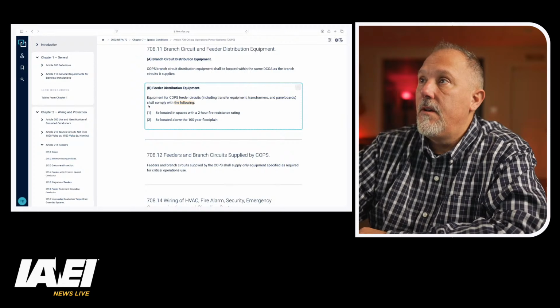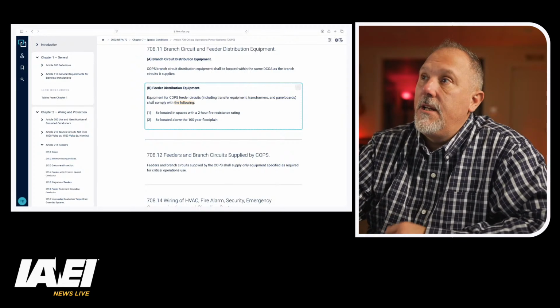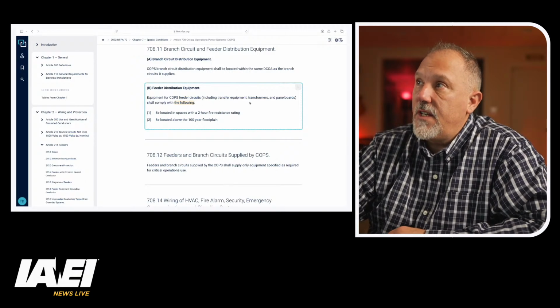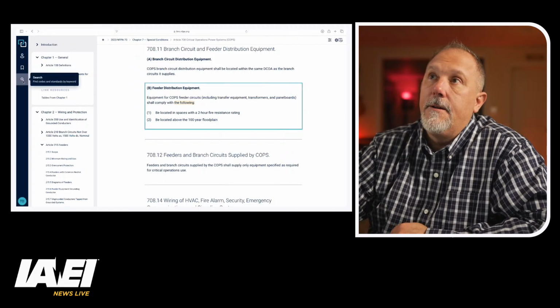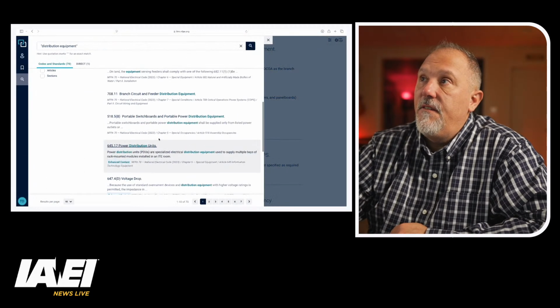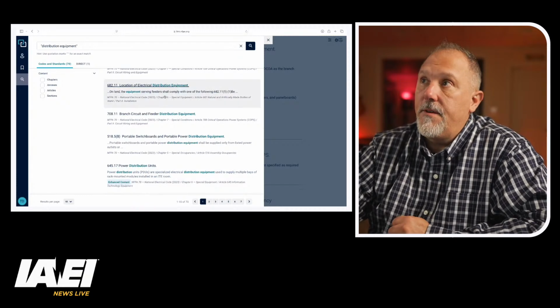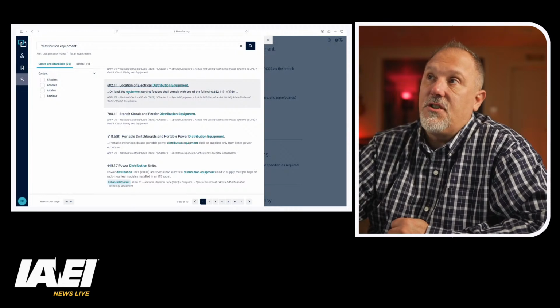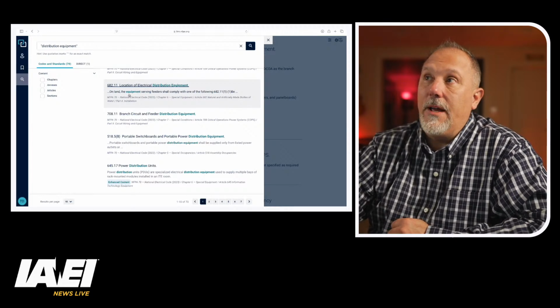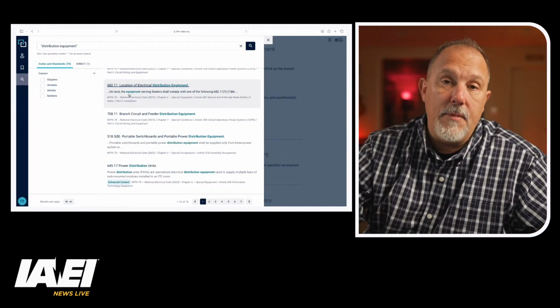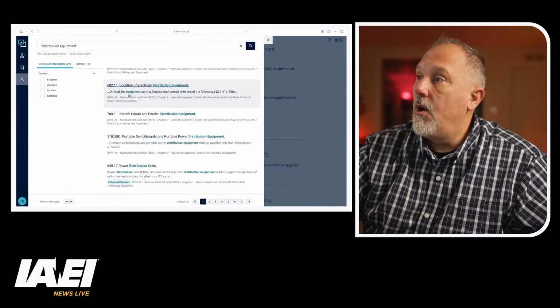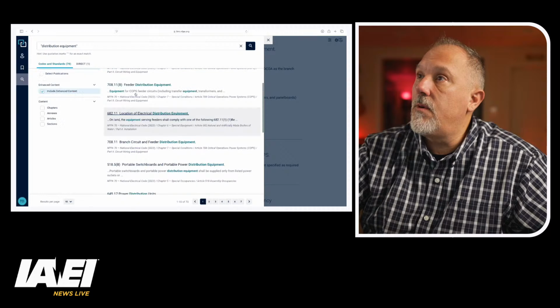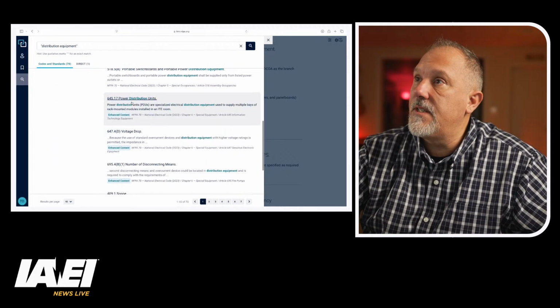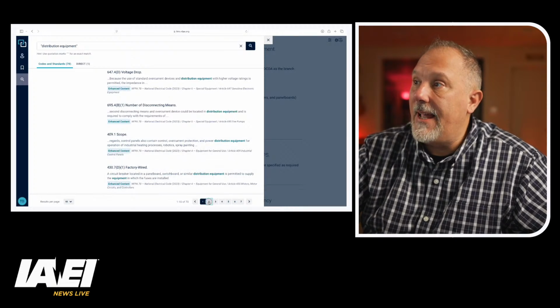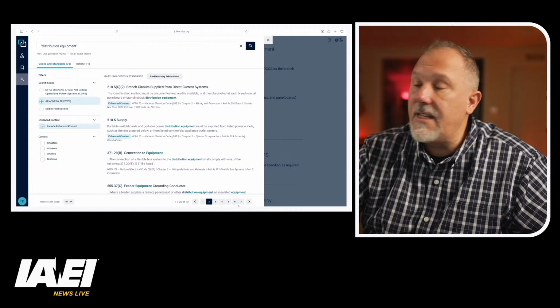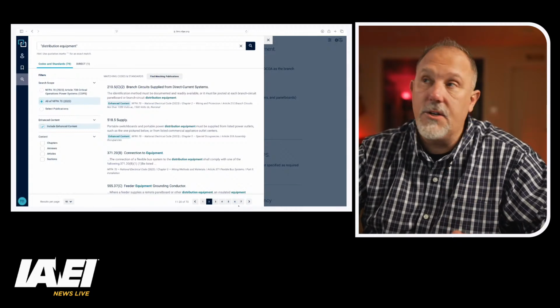Feeder distribution equipment. That's the name of the entire section. Equipment for COPS feeder circuits, including transfer equipment, transformers, and panel boards, shall comply with the following. So we use the term feeder distribution or distribution equipment. Location of electrical distribution equipment, 682, serving feeders. So if we don't know what it means in that exception, then I would argue, Ryan, what are you doing about each one of these? 1, 2, 3, 4, 5, 6, 7, 8, 9, 10. That's 10, 20, 30, 40, 50, 60, 70, over 70 locations in the code where we use the term.